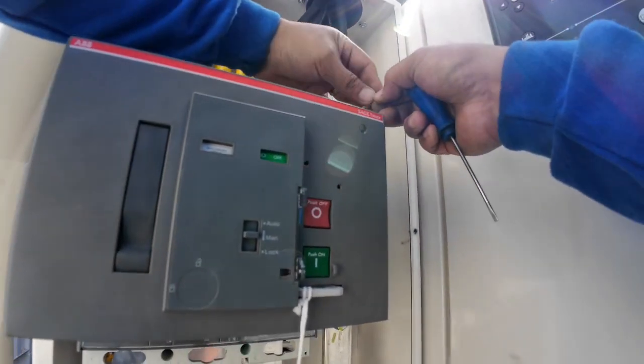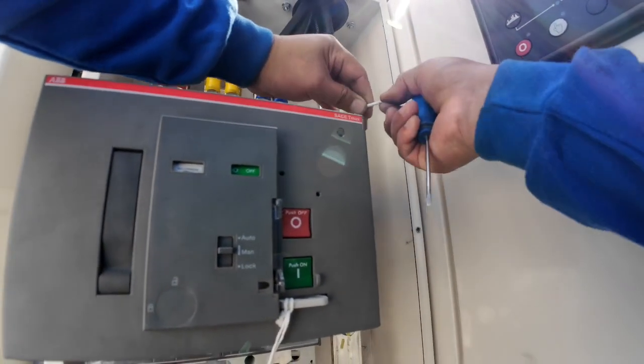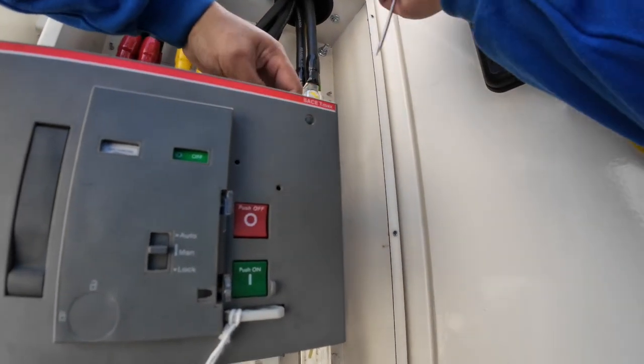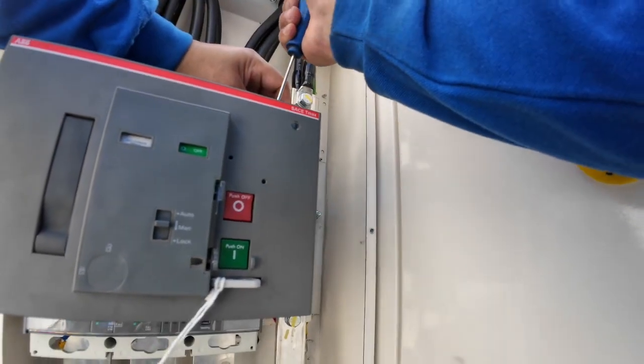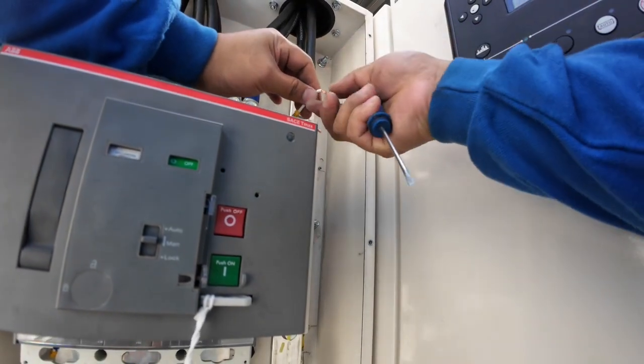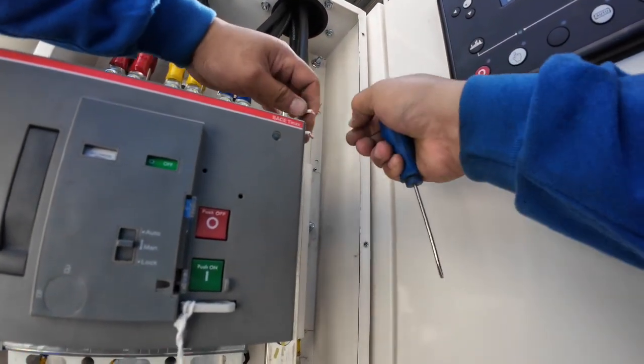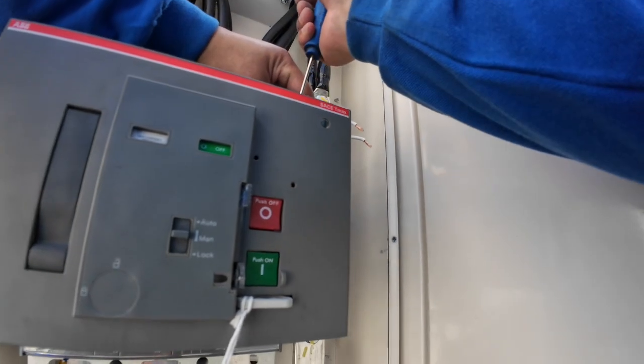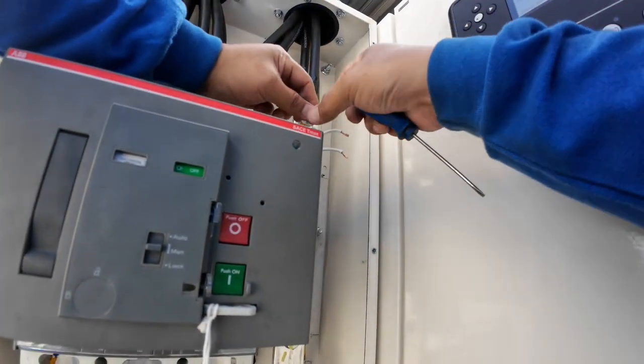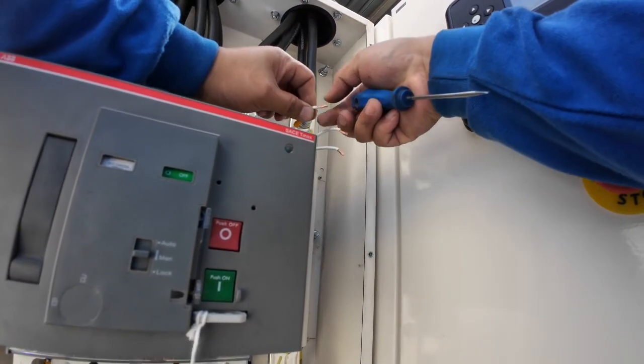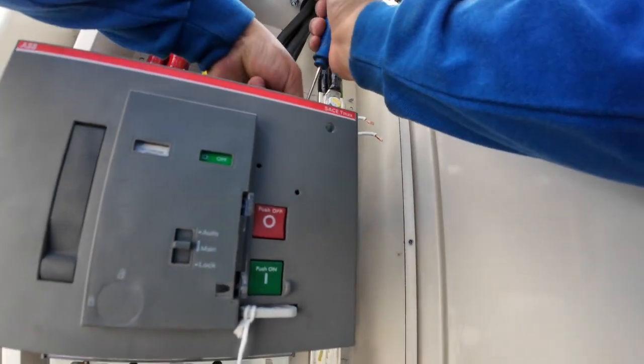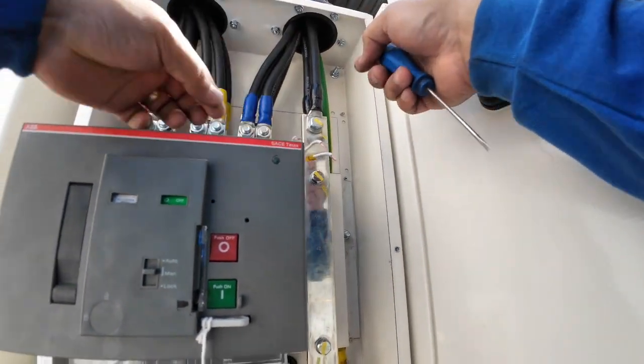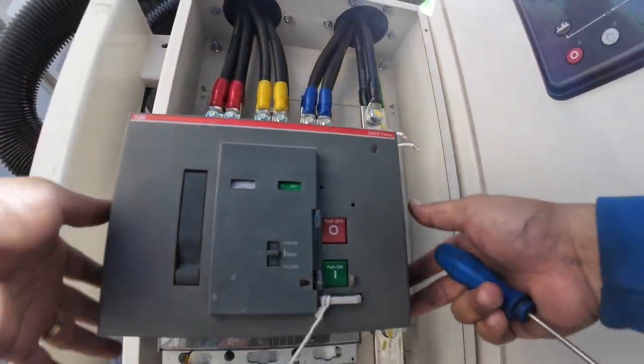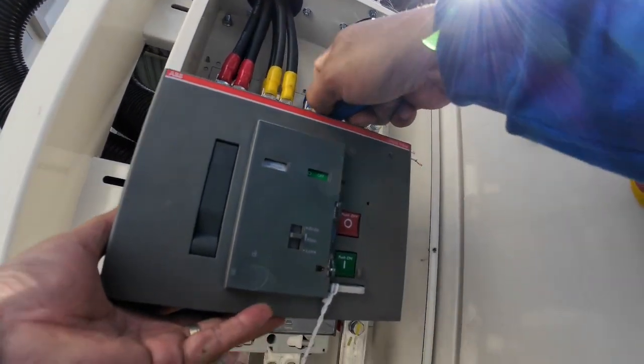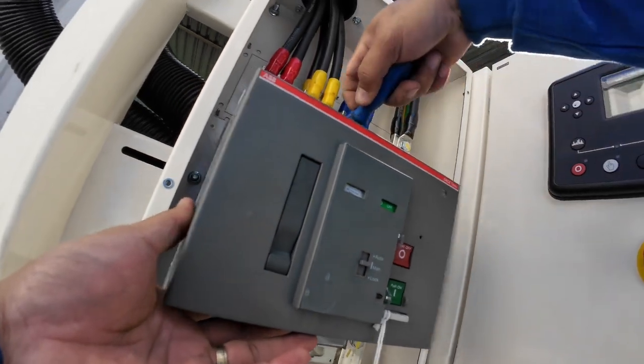So if you open up this type of breaker, you need to remove the connections at the top, so it will not give you difficulties or any issues when we open the breaker, because this one can cause you some problems during the removal of the cover. So this one is to be removed first, and after that, if it is done, you need to fix it back and also make sure the wiring is correct, and don't make a mistake, because either it will burn your motor or your limit switch from inside.